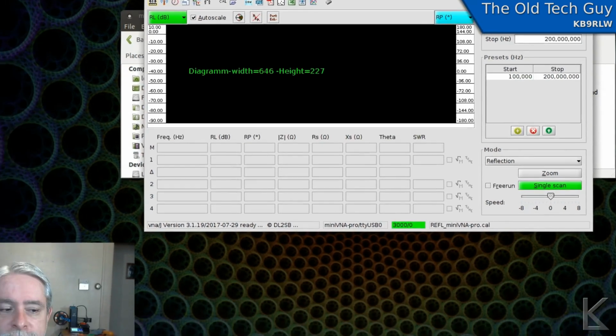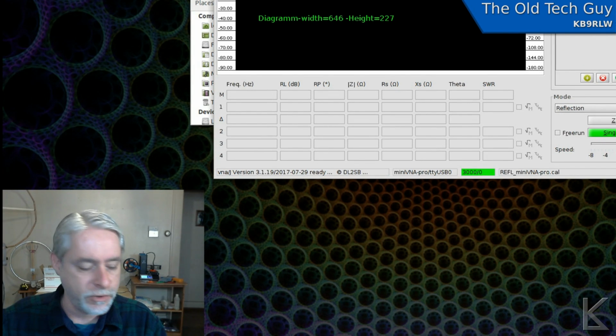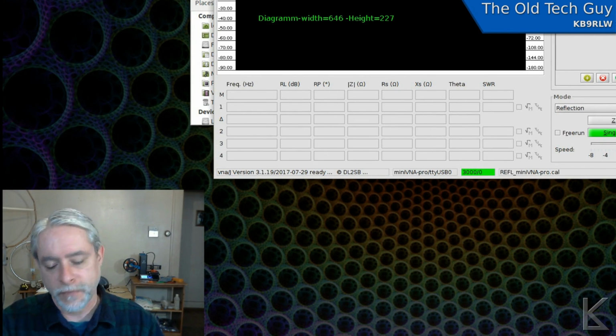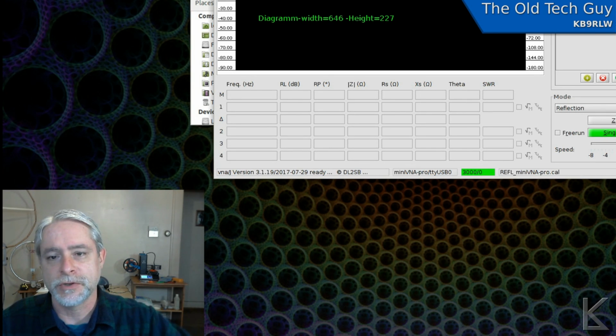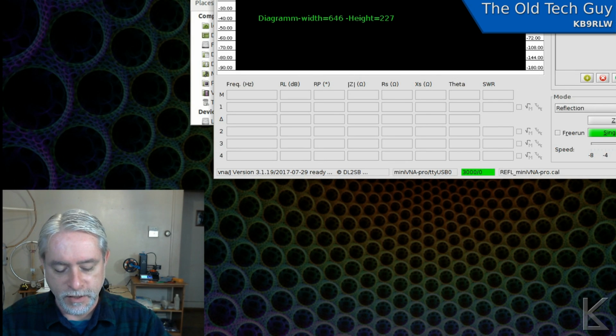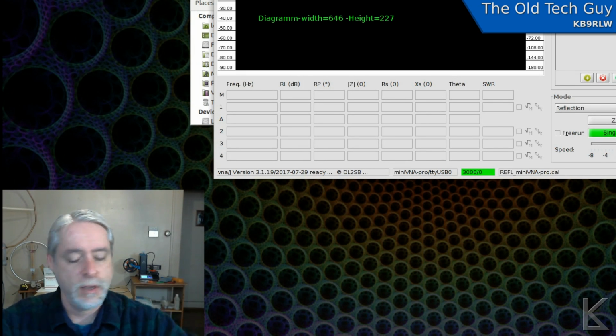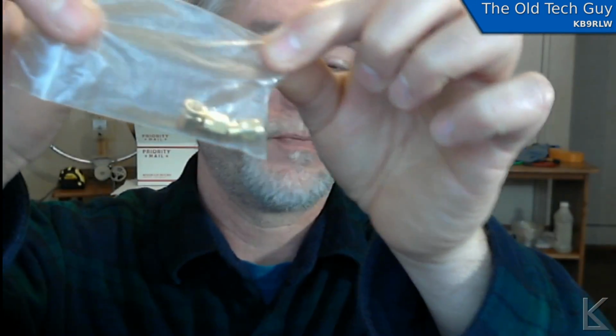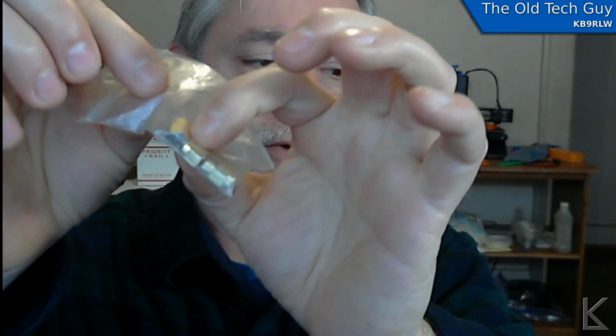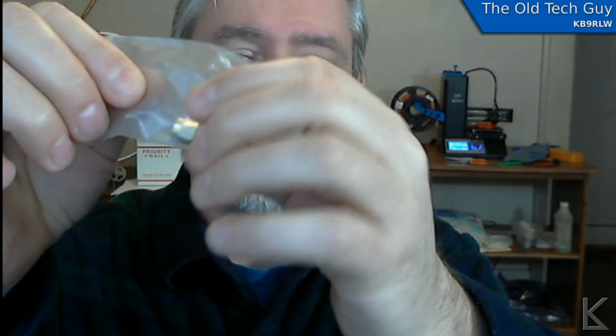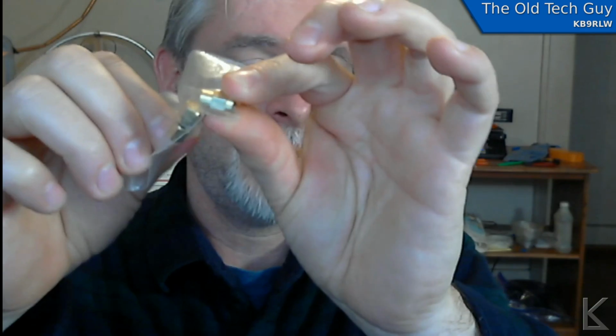The first time that you run this software, it's going to want to calibrate your unit. It creates a calibration file that it uses so it knows the baseline for the unit, because every unit's going to be a little bit different in the electronics. You need to calibrate it. And they provide you with these little calibration plugs here. There's 3 of them, and they're engraved on the sides. They're little SMA plugs, and they're engraved on the sides with open, short, and load, which is a 50 ohm load. The calibration steps, and I'll open the dialog here so you can see it.